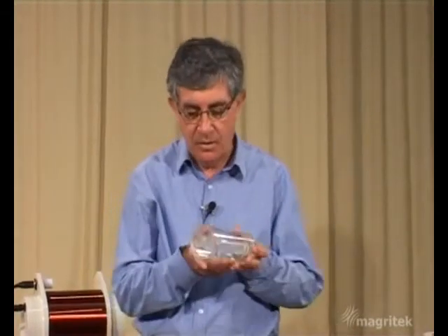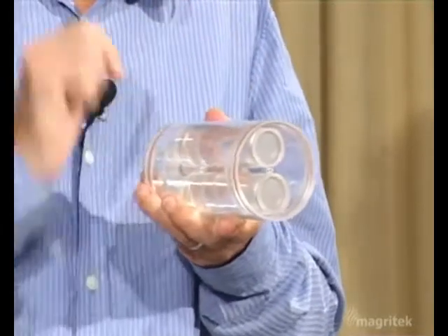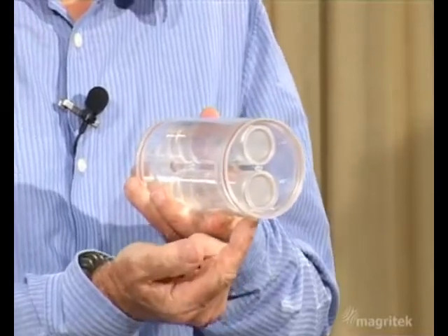In this video, we're going to be looking at magnetic resonance imaging. And we're going to carry out one of the simplest imaging experiments possible on a very simple sample comprising these 2 tubes of water. Remember that the Larmor precession frequency of the nuclear spins depends upon the strength of the magnetic field. Now just imagine if we could make the magnetic field higher on the top tube and lower on the bottom tube. That would mean that the top tube would have a higher frequency and the bottom tube would have a lower frequency. And if we looked at the spectrum of that, we should see 2 signals at 2 different frequencies corresponding to the 2 tubes of water.